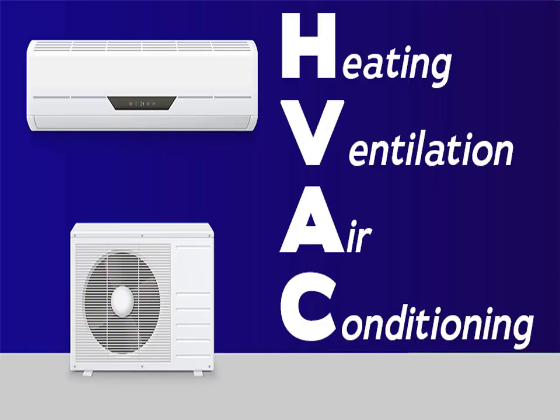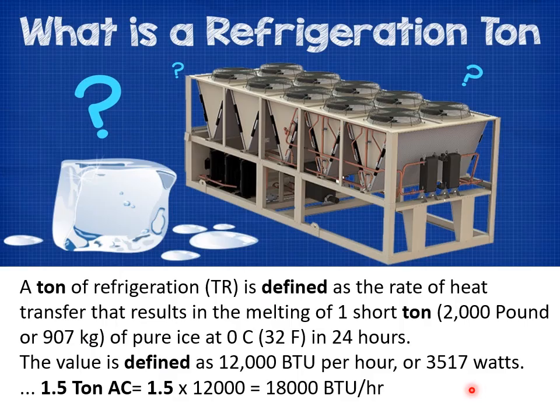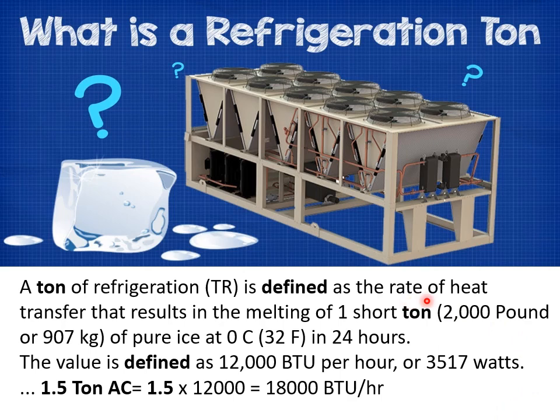HVAC stands for Heating, Ventilation, and Air Conditioning. The capacity of an air conditioner or HVAC chilling plant is measured in tonnes of refrigeration (TR). A tonne of refrigeration is defined as the rate of heat transfer that results in the melting of one short tonne (2000 pounds or 907 kg) of pure ice at 0°C in 24 hours. The value is defined as 12,000 BTU per hour or 3517 watts. For example, an air conditioner of 1.5 tonnes has a capacity of 18,000 BTU per hour.